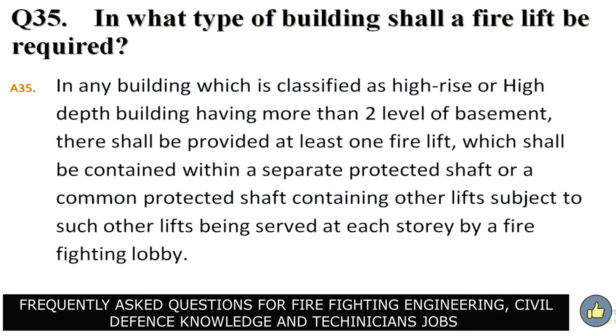Question number 35. In what type of building shall a fire lift be required? Answer. In any building which is classified as high-rise or high-depth building having more than 2 levels of basement, there shall be provided at least one fire lift which shall be contained within a separate protected shaft or a common protected shaft containing other lifts, subject to other lifts being served at each story by a firefighting lobby.